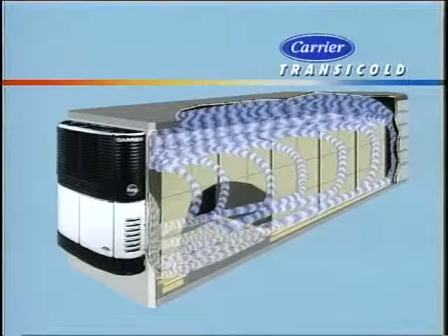The front doors of the unit are opened by releasing a single latch. This Carrier refrigeration system is powered by a 4-cylinder Kubota diesel engine. The engine is direct coupled to a 6-cylinder compressor. The engine power will also turn the gearbox, which is then connected to the fans and the alternator. All of these components are connected with belts. However, in most cases you will not be able to see them because of the belt guard.